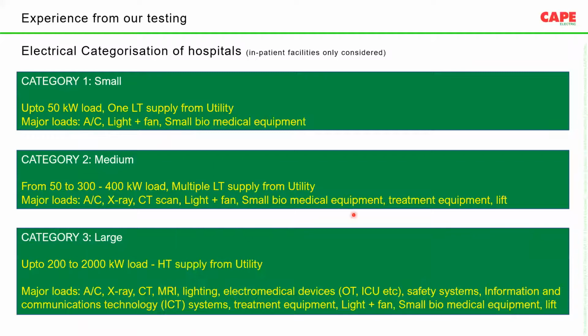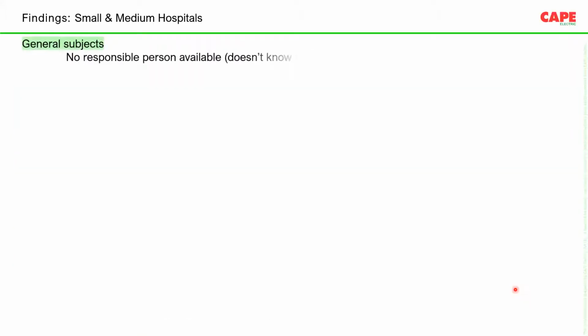And the third one is the category large. These are hospitals with really high voltage supply, 11 kV, 20 to 33 kV supply. There is a transformer and the low voltage is fed into the hospital. Major loads are again air conditioners, X-ray, CT scan, MRI, lighting, electromedical equipment, safety systems, and so on. You can note down here, these are some of the equipment used in these hospitals.